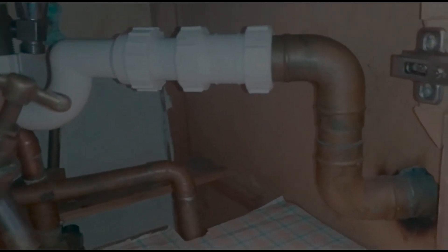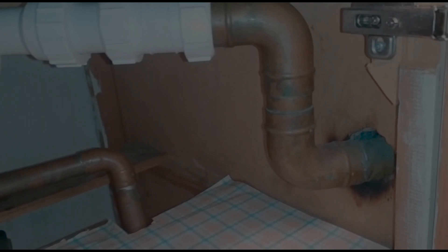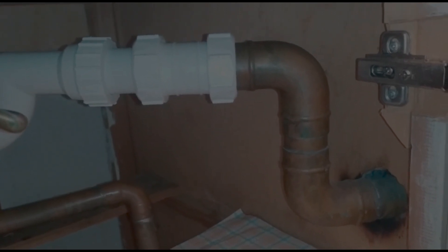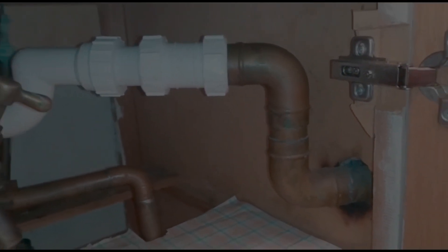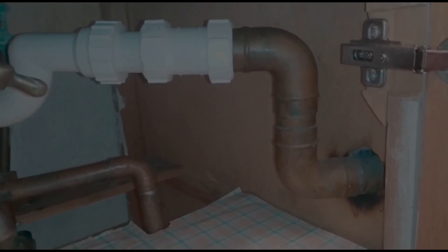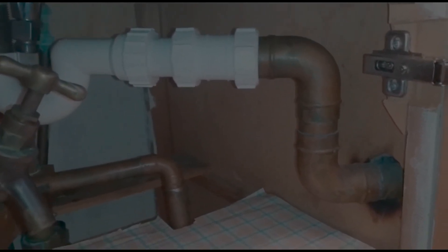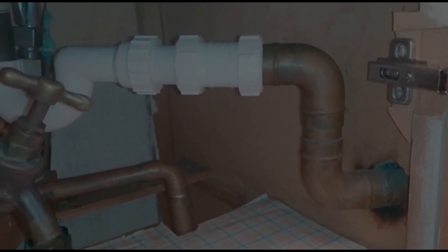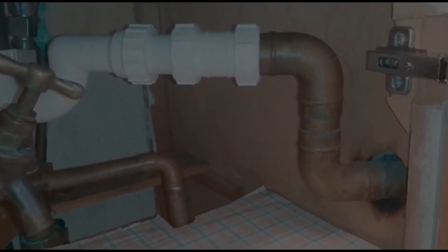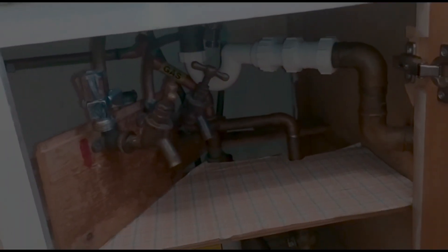If you don't, and you find a copper sink waste that you were going to tee into, well, you can't. This copper waste goes right the way through into the bathroom behind into a cast stack, which really are not meant to tee into cast stacks because the condenser pipe is acidic. Now you could put a neutraliser on it, but as we all know, who actually changes the neutralisers every 12 months? Look how old this setup is in here. It's amazing.